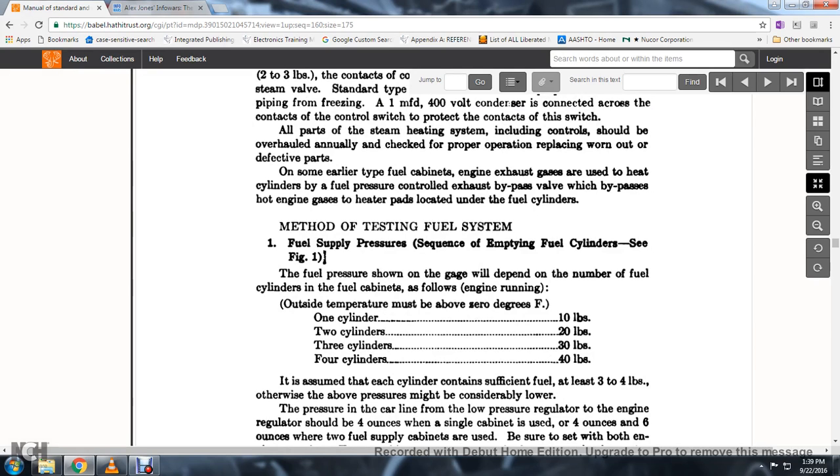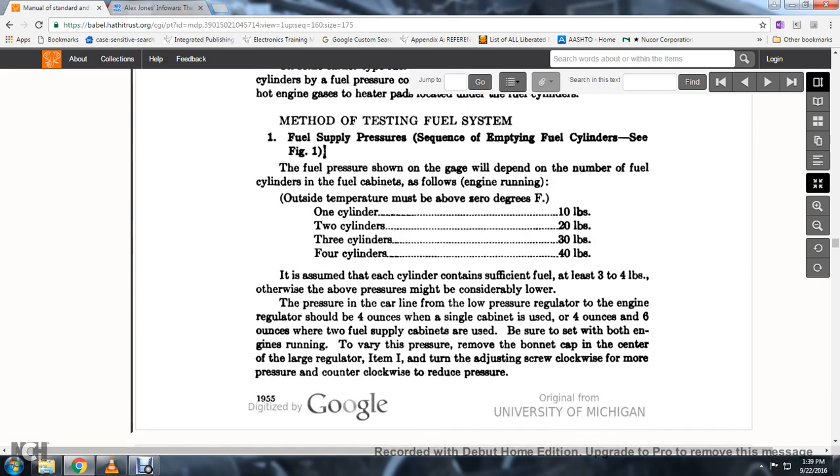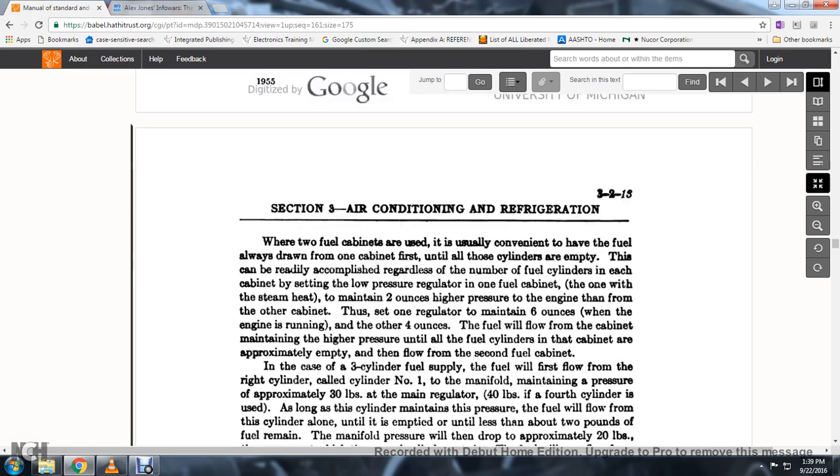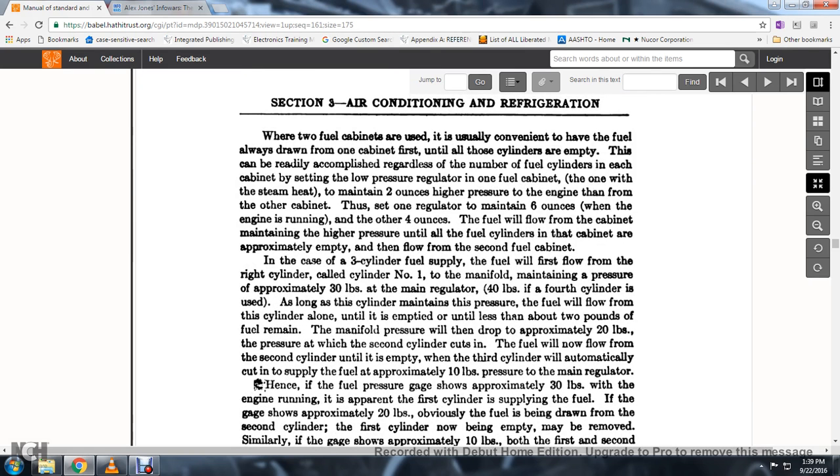It is assumed that each cylinder contains sufficient fuel — at least three to four pounds — otherwise pressure might be considerably low. The pressure in the car line from the low pressure regulator to the engine regulator should be four ounces when a single cabinet is used; 4 ounces and 6 ounces where two fuel supply cabinets are used. When setting pressure with the engine running, remove the bonnet cap in the center of the large regulator, item I, and turn the adjusting screw clockwise to increase pressure and counterclockwise to reduce pressure.